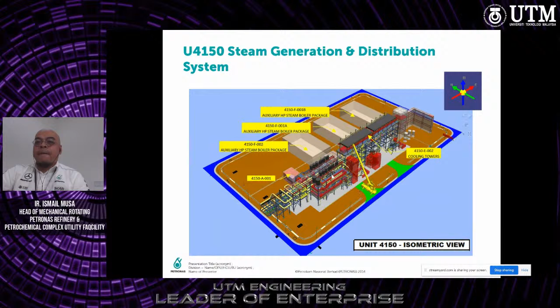The other area is HP steam, which is also self-generated and distributed internally by SCC, the steam cracker plant. They also produce steam, and have an excess steam recovery system, which we call 3R. So this is the steam generation and distribution system. This just shows some of the layout of the cogen plant. We have auxiliary boilers, the cooling towers, and also the gas turbine for this unit.